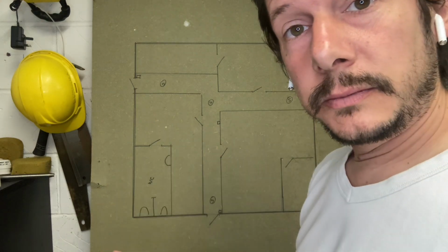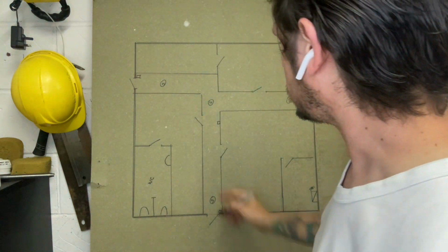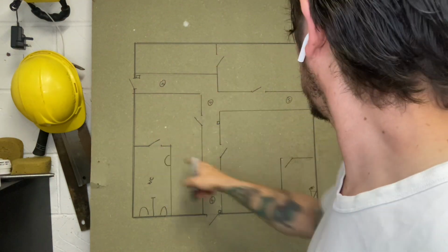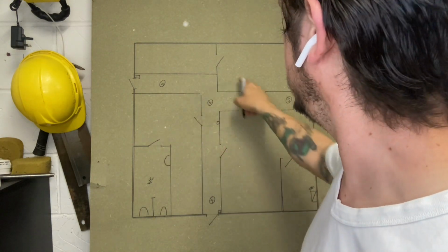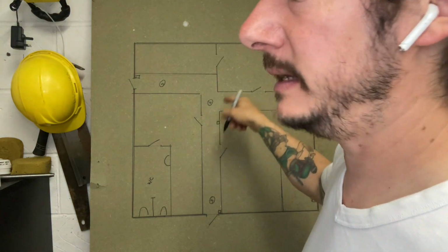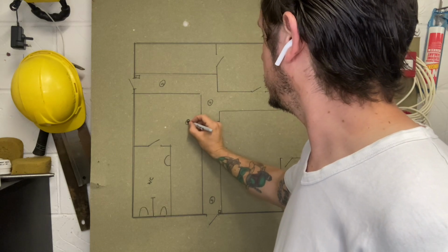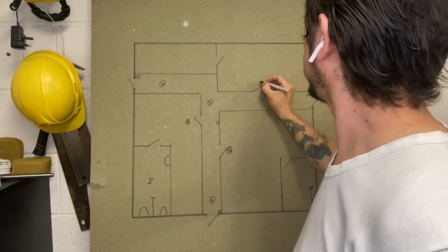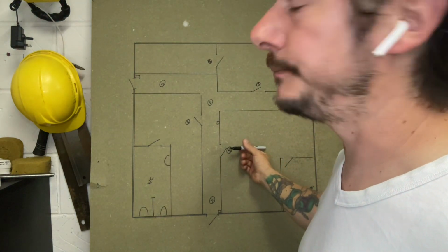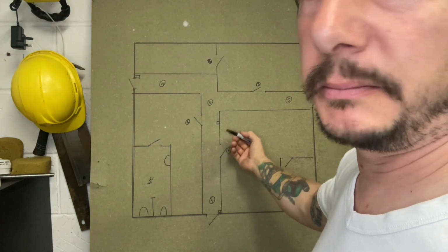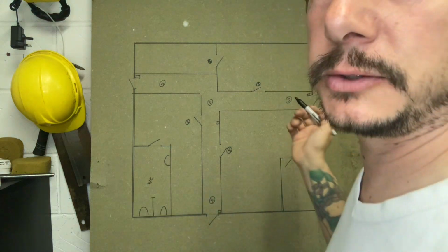L3, doors that lead onto escape routes. So if these are all true fire compartments, then these are all fire doors, but this is the escape route. So we are interested in keeping an eye on these. These doors will be automatically closed. If they're held open, that's a £1,000 fine for whoever holds it open. So you would have detection around here, keeping an eye on these doors. Straightforward enough. You're even allowed to mount them above the door on the wall. Check with the ceiling heights, manufacturer stuff. I'm not going to spoon feed it all to you here.